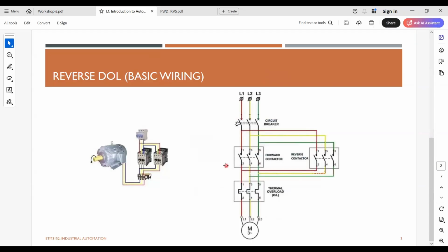Now, forward reverse motor starter, also known as the reverse DOL or the reverse direct online starter. Basically, you need to use two contactors. In the forward DOL, you just need to use a single contactor, but when it comes to reverse DOL, you need to have two contactors. And for the protection, you have the main circuit breaker, as well as for the protection of the motor, we have the overload relay. So take a look at this wiring diagram.